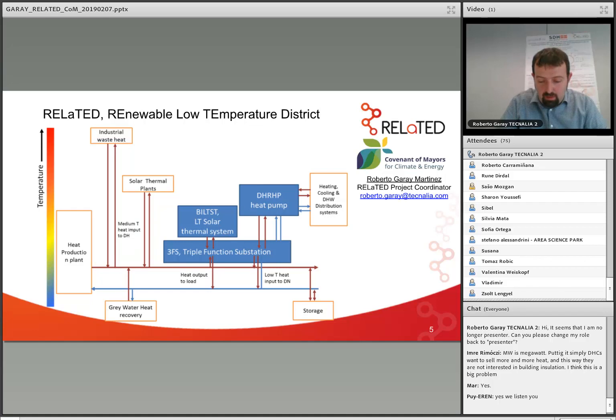So the core of everything is a substation, which allows for what we call triple function substations. The first function is the traditional one in district heating, which is to get heat from the network and put it into the building. It also allows managing solar plants in the building, which is the second function. And by matching it with a heat pump system, a reversible heat pump system, it allows pumping heat into the network coming from cooling applications at building scale.